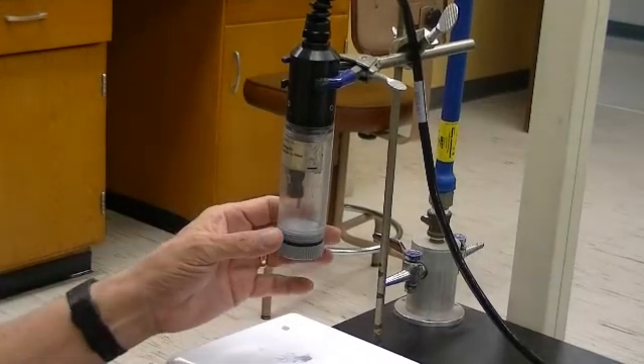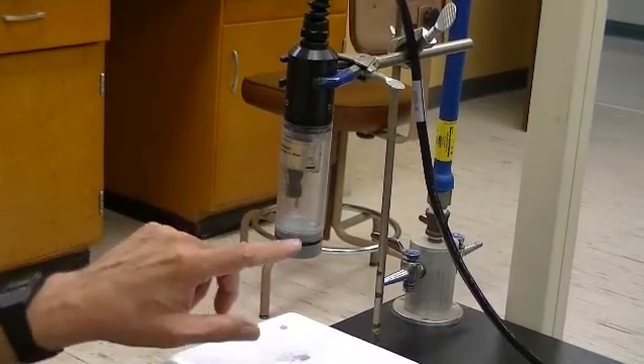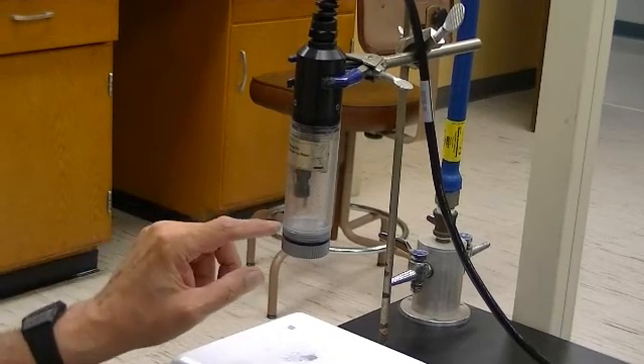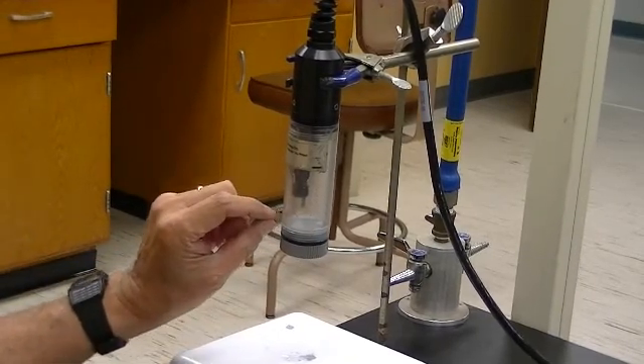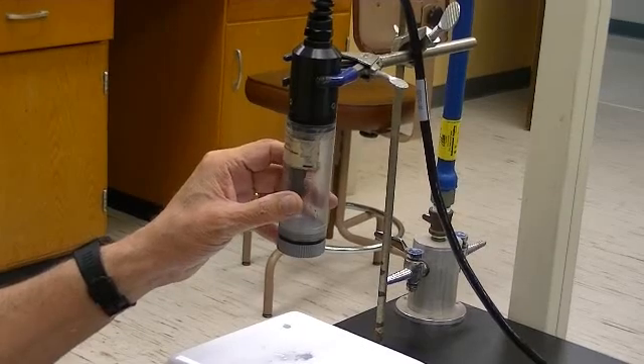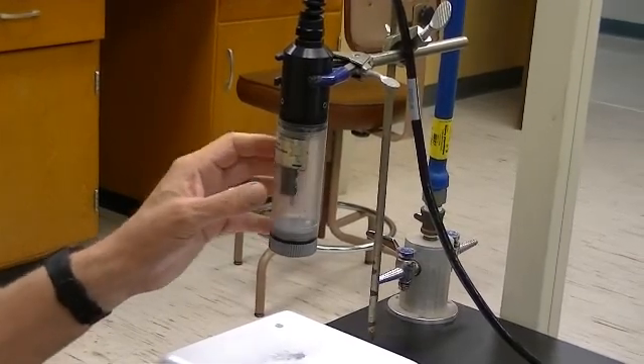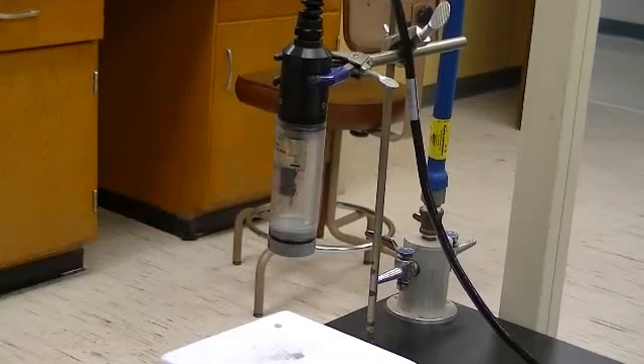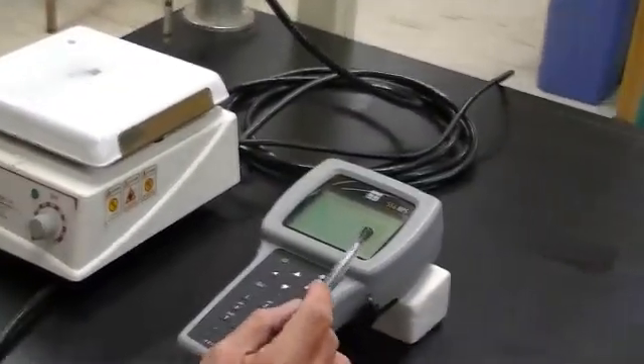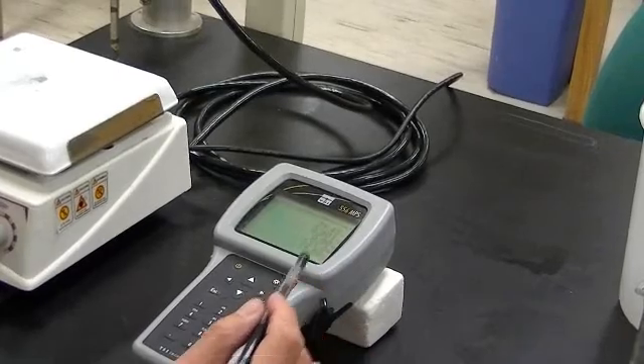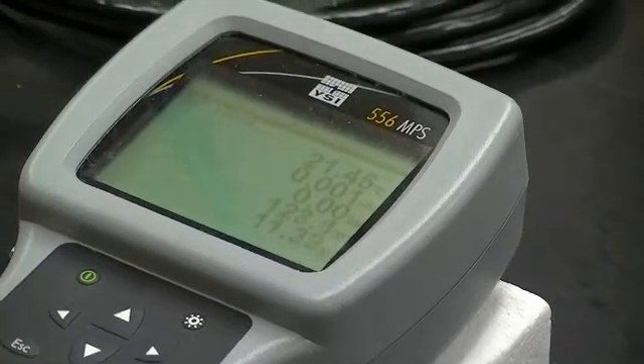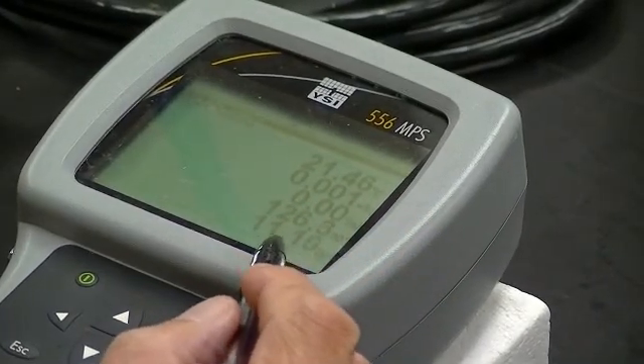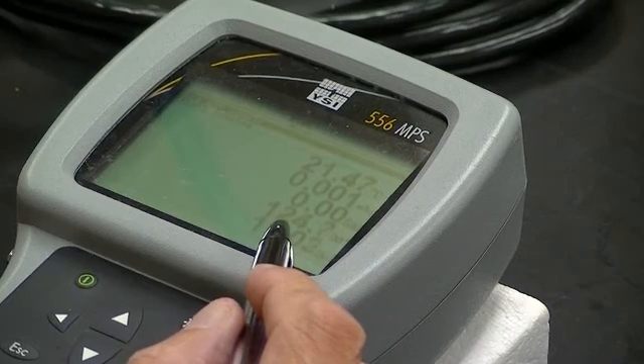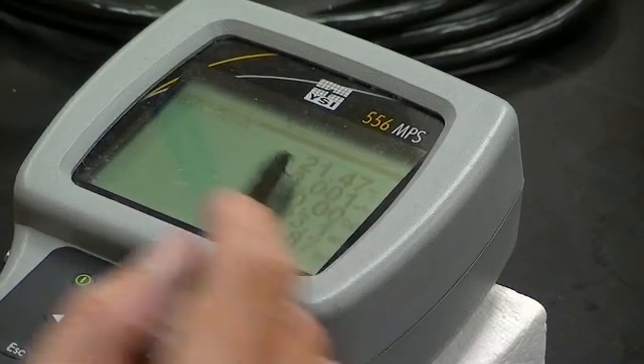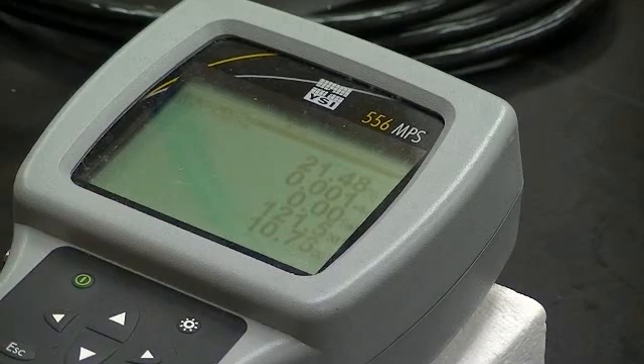I've obviously recalibrated it, but the chamber is empty except for just a teeny little bit of water. Okay, and the chamber is on there kind of loosely, not completely screwed in against the O-ring. Now, when you turn the instrument on, the bottom two numbers are the numbers that you're primarily interested in for the calibration. And the bottom number is the dissolved oxygen concentration in milligrams per liter, and the second number from the bottom is the percent saturation.